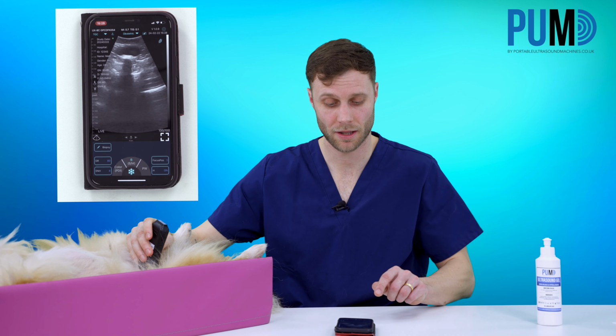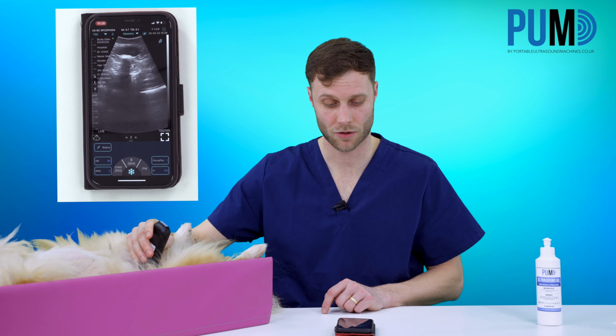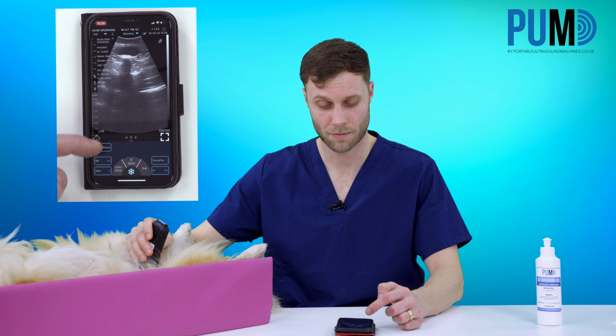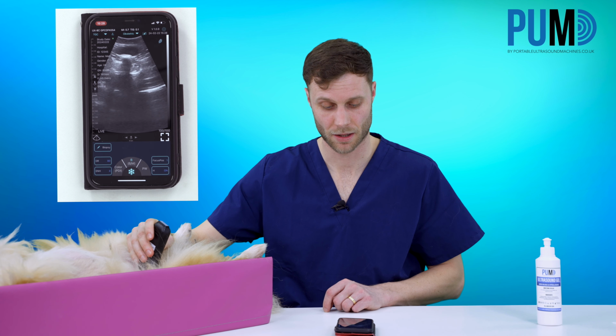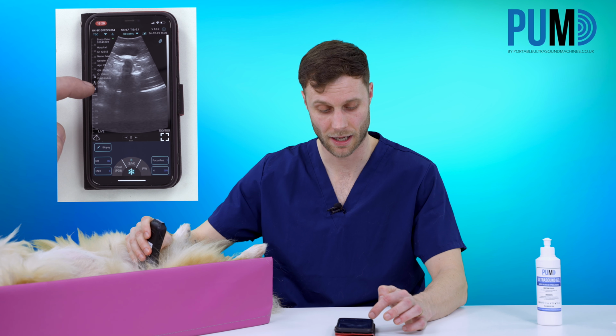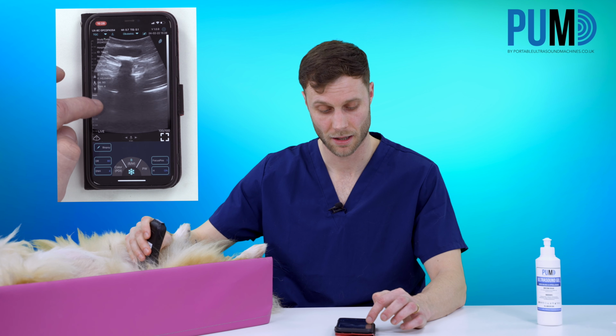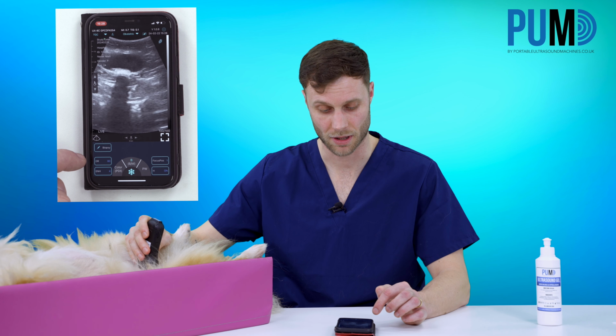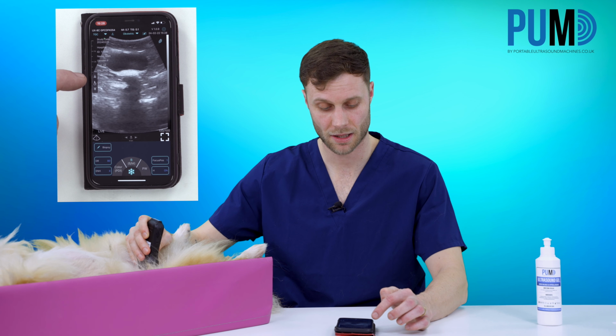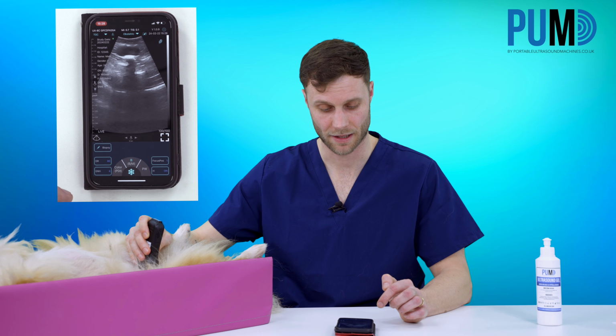Introducing depth. For this example, we are going to scan a bladder on a dog, and we're going to go through some of the controls you might want to optimize when scanning. Firstly, depth. As we can see on this image, we have the bladder at the very top of the screen, but we have a lot of space beneath that we're not interested in. So what we want to do is reduce the depth to highlight the bladder. For that, we have a little arrow on the side and we can scroll down to reduce the depth. If you want to increase the depth, simply scroll up on the left hand side.